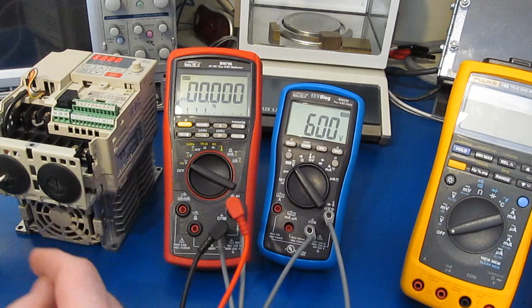This is currently programmed for 60 Hertz. Both meters are again in parallel. Let's go ahead and look across two of the phases. This is a three-phase controller, and you can see it's roughly 248 volts.